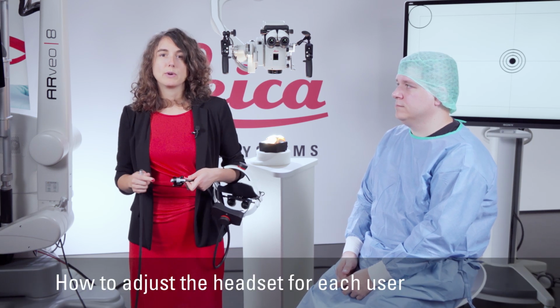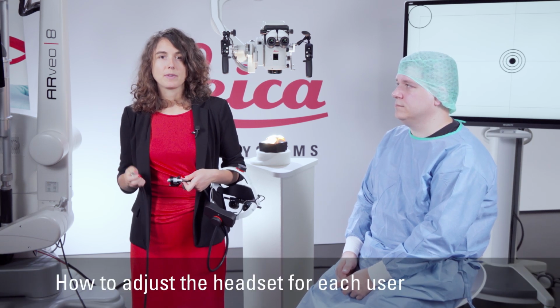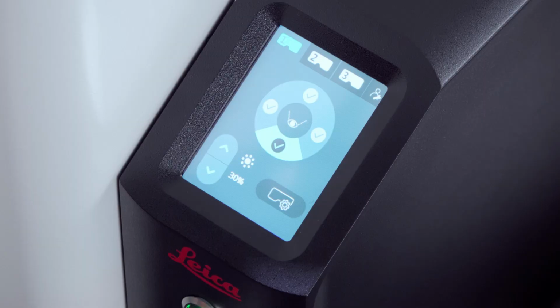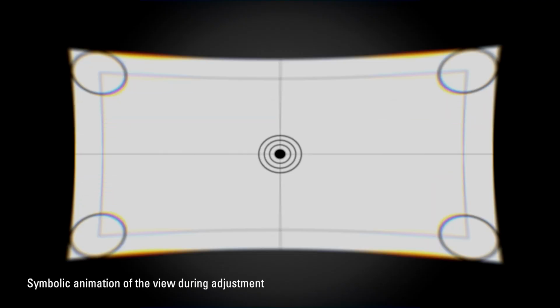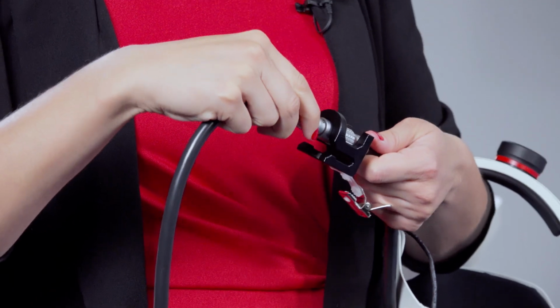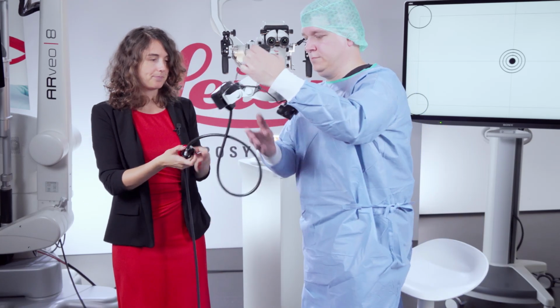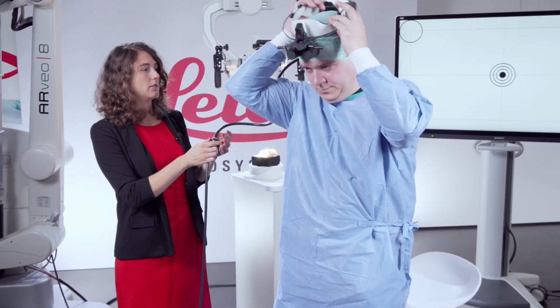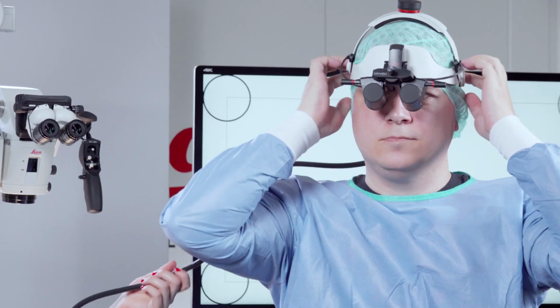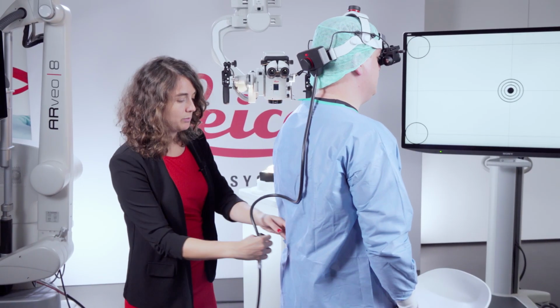In order to get the most performance out of MyVeo, the user needs to adjust to his own physiology. First, you need to switch on the adjustment image on the hub. This image is here to be able to adjust the headset independently from the settings of the microscope. After this step, you need to plug the headset to the cable. Here. The user puts it on the head, and the cable needs to be attached to the back.